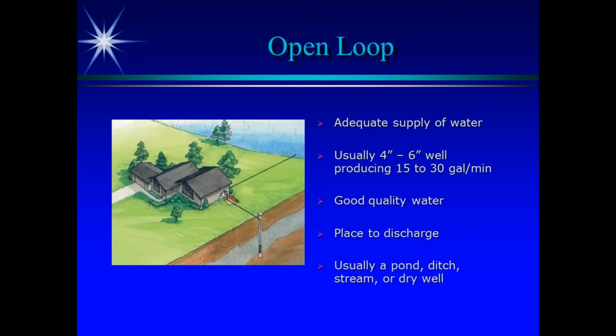Here you usually need a 4 or 6 inch well that produces 15 to 30 gallons per minute, with good quality water. The key is you need a place to discharge it, usually a pond, ditch, or stream. So if you're near a ditch you can discharge into it, or if there's a lake or pond nearby, you can do that.